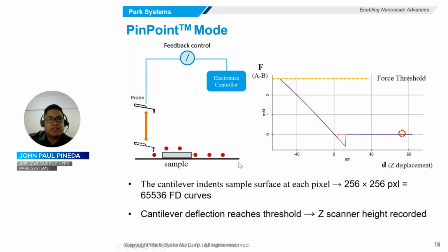Okay, so now let's proceed with Pinpoint mode. During operation, while measuring sample morphology, the XY scanner stops at each acquisition. And during this pause, the Z scanner takes a rapid FD curve with finely controlled force, distance, and contact time between the tip and the sample. In brief, an AFM probe approaches and indents the sample surface at each pixel within the area to be imaged. For example, if the cantilever indents the surface at 256 by 256 pixels, we will expect to have about 65,000 force distance curves generated to map the sample mechanical properties. Once the cantilever deflection reaches the force threshold, the Z scanner height is recorded, and reconstruction of which will give the topography information of the sample.